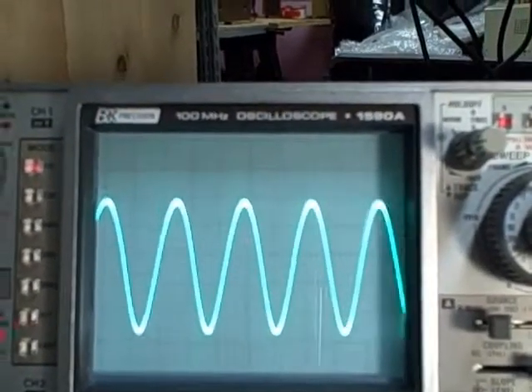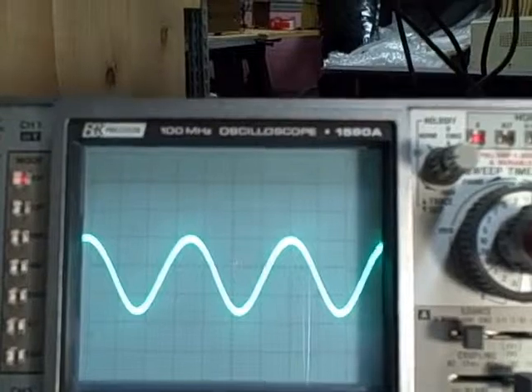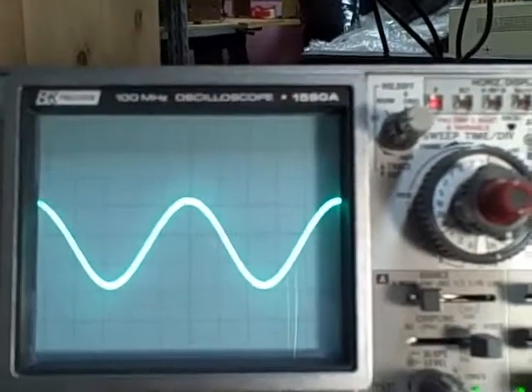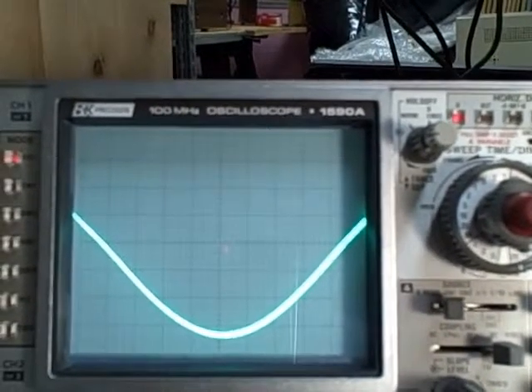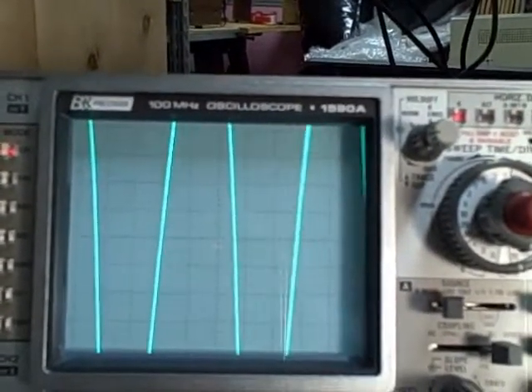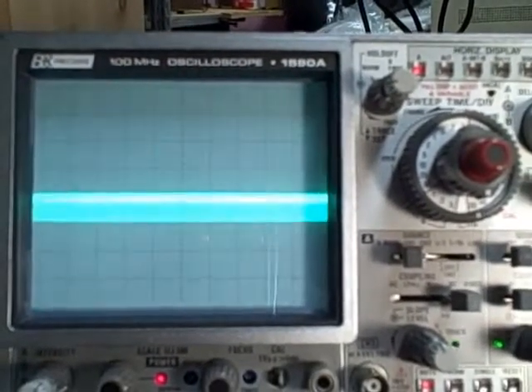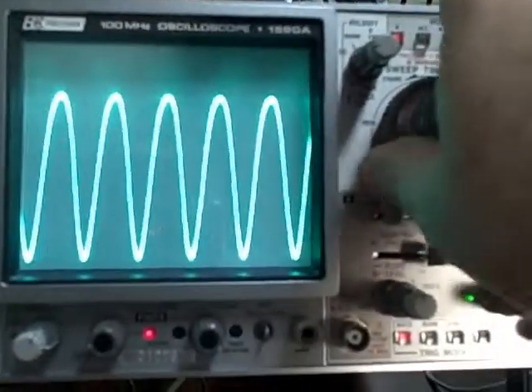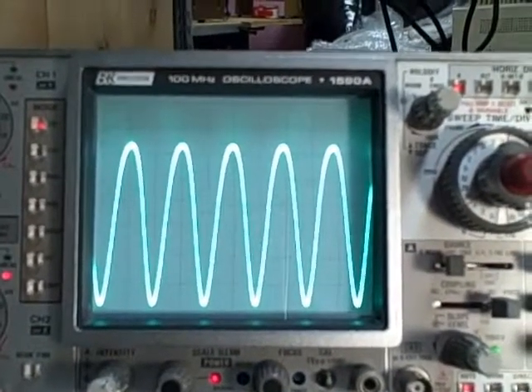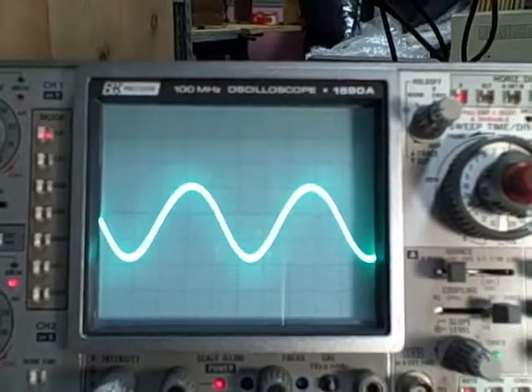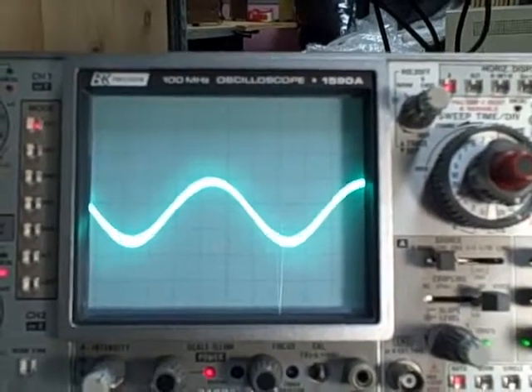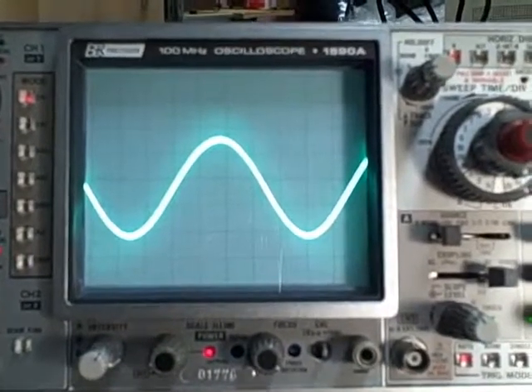We've already swept through Band F. I am now on Band E, the second band down. We're at maximum, and as I sweep down you can again see the waveform expanding. You also see the amplitude going down a little bit, so I'll kick up the amplitude with the manual control. I'll switch to the 3.1 to 11 megacycle band, take us back up to the top end, reduce amplitude so we can see the waveform a little better, and reduce frequency.